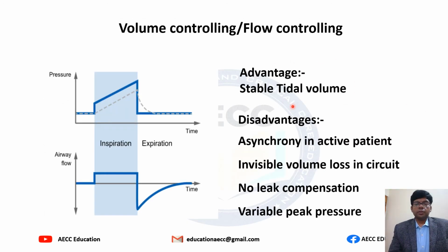Now, let's discuss it one by one. The first one is the volume controlling. As we know, flow is equal to V by T, that is volume by time. So flow is also controlled here. But look here, the flow is constant, square wave pattern, but there is change in the pressure. The advantage of volume control mode is the stable tidal volume, but there are certain disadvantages as well. More asynchrony in case of the active patients.